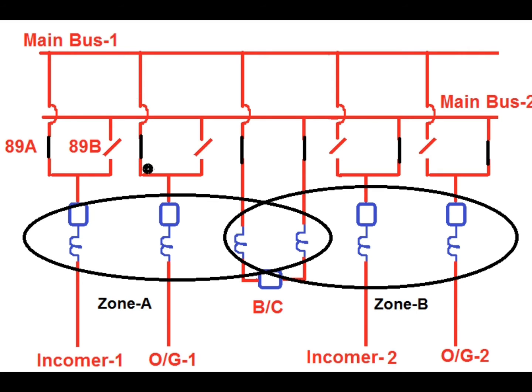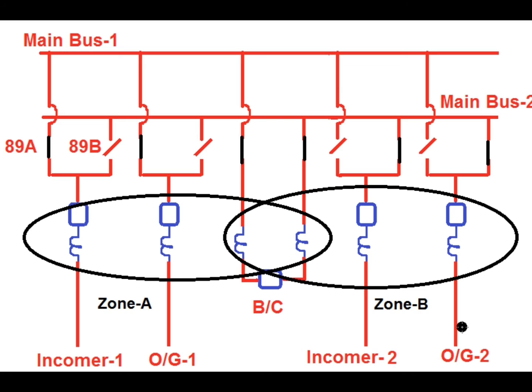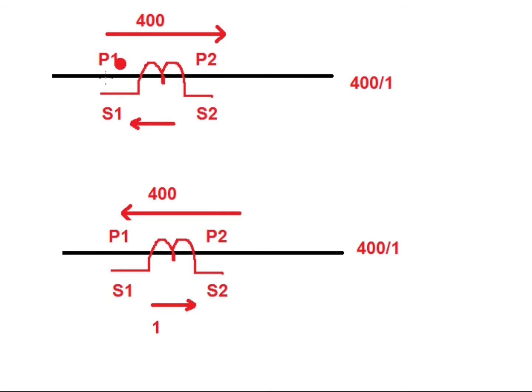Similarly, if outgoing feeder 1 is connected towards main bus 1 via 89A, then this outgoing feeder is also considered in zone A. The bus coupler CT connected towards main bus 2 will be counted in zone A, and the bus coupler CT connected towards main bus 1 will be considered in zone B. Incomer 2 is connected to main bus 2 via 89B, so incomer 2 is considered under zone B, and outgoing feeder 2 connected to main bus 2 via 89B is also considered under zone B.